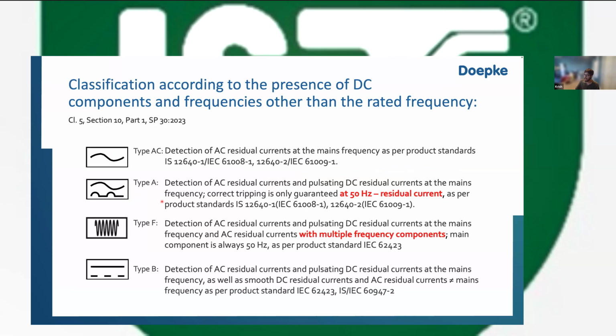So yeah. Now, when it comes to achieving this disconnection, it's very important that the correct classification of RCD is chosen. There are 4 types of RCDs available in the market. This is not about the RCCB, RCBO, or CBR, MRCD. This is to do with the classification according to the presence of DC components and frequencies other than their rated frequency.